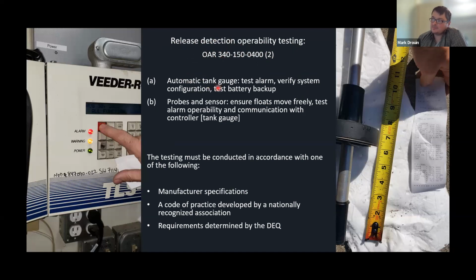We want the tank gauge to be tested, and we call out that you want to test the alarm, verify the system configuration, and test the battery backup. So here's a Veeder-Root at a facility. A lot of questions come up, like, well, what alarm am I testing? Because there's a bunch of alarms on these facilities. People are familiar with the overfill alarm, but there are various others. And we're not asking for the overfill to be tested yearly. You can, but we're not asking to. We're not talking about that.